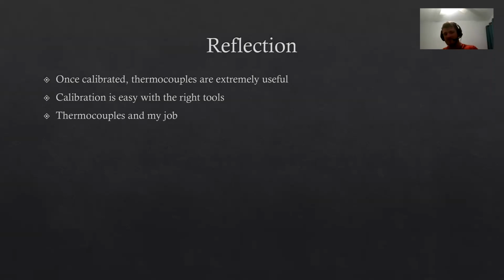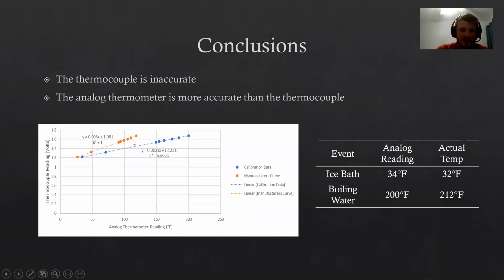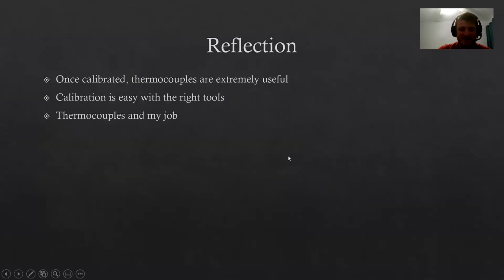Because of how wrong the thermocouple was, I'm not sure if we can actually calibrate it to read correct values. The lower voltage, lower temperature values were pretty close, but as we can see in this graph, at the higher temperature it's 100 degrees Fahrenheit off. Even if we say that at 1.7 volts it's supposed to be 200 degrees Fahrenheit, I think there's just a high enough inaccuracy that I wouldn't really trust the thermocouple, at least this one, to read any of my temperature values. But other than that, this is a great project.